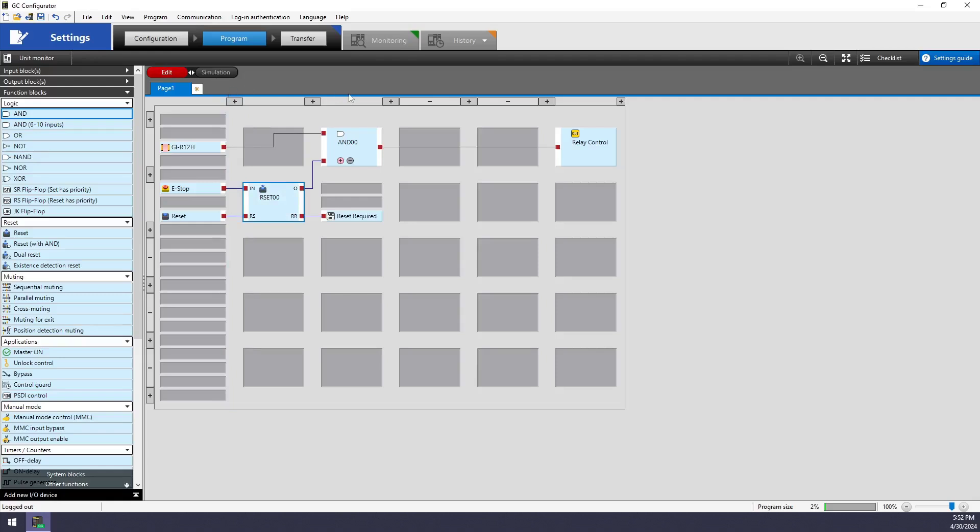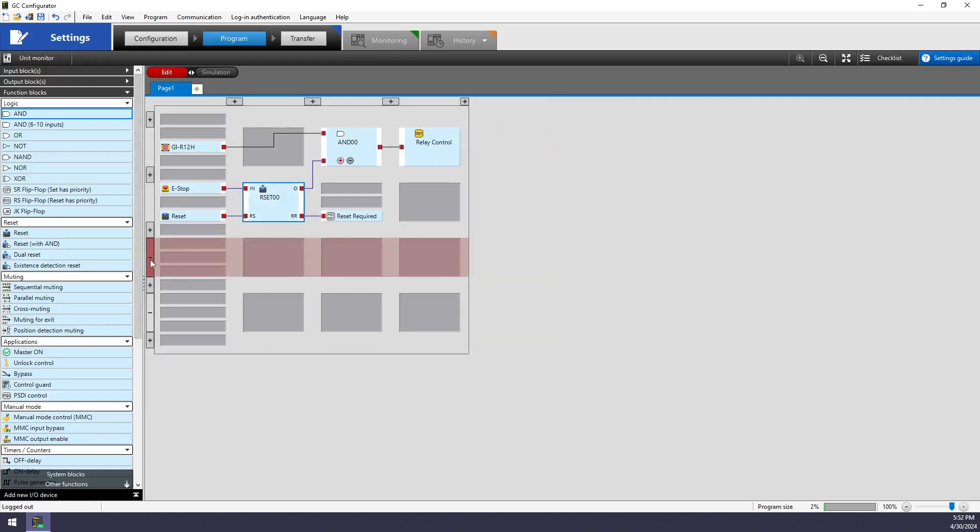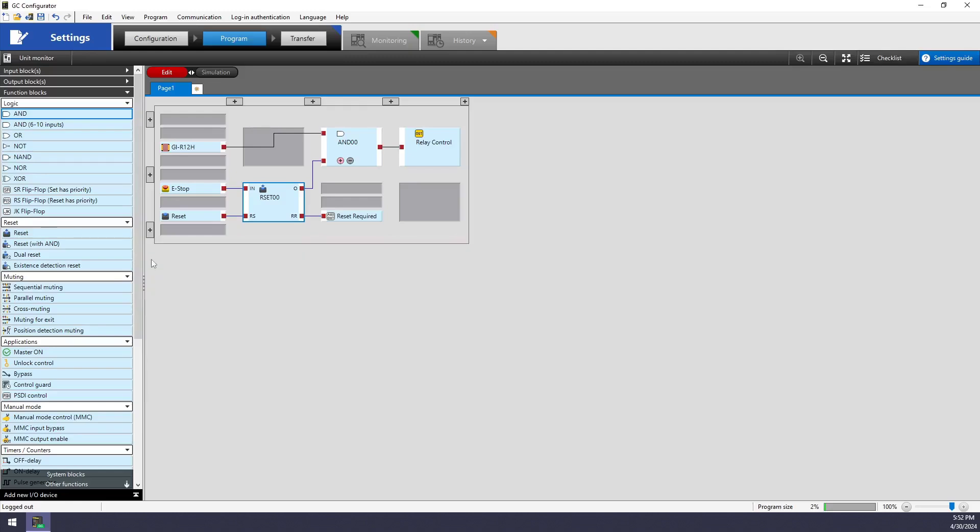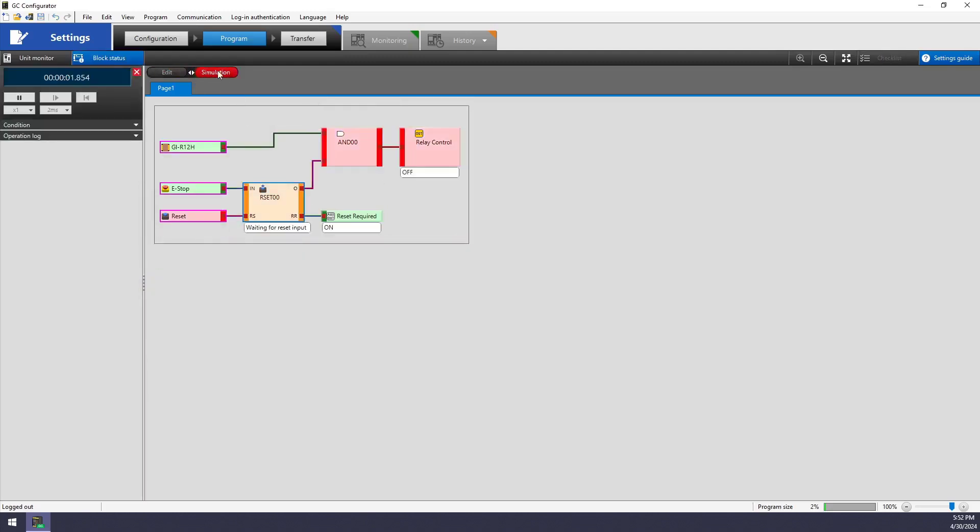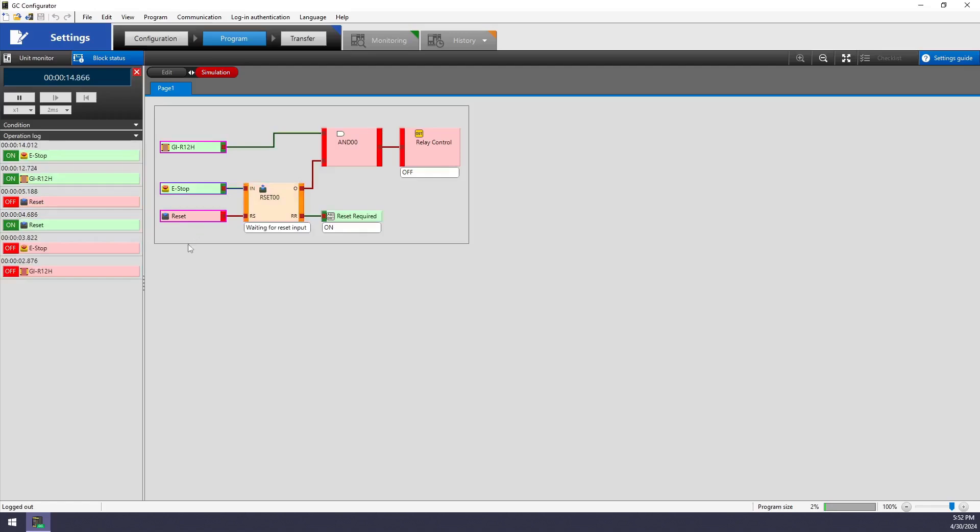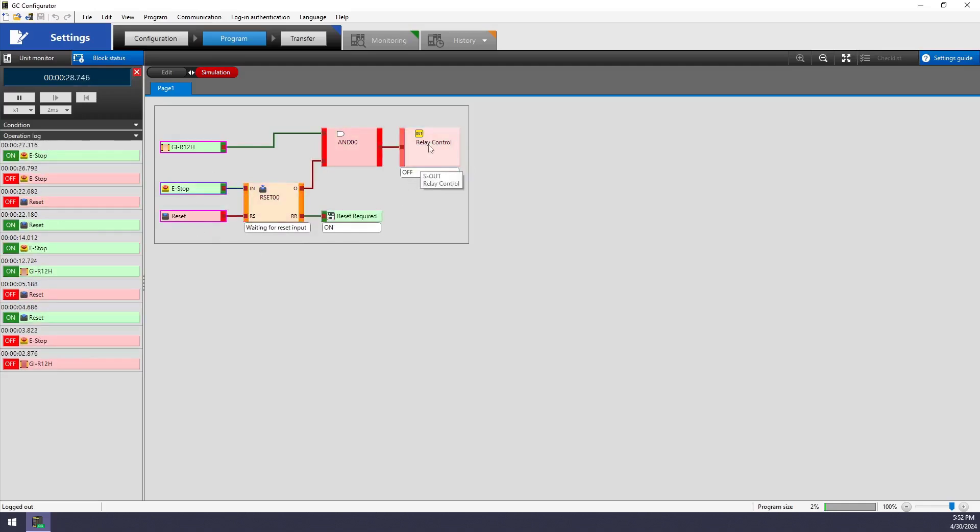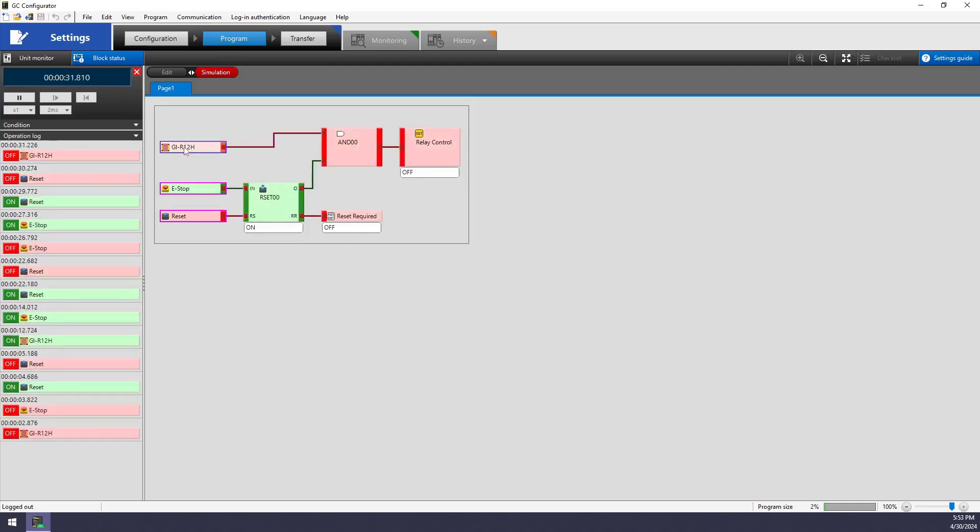I'm really done programming now, but what I always do before I transfer it over to the GC is to simulate and make sure that the function is as I intended. So by clicking on any of these input devices, you can simulate them going from a safe condition to an unsafe condition or pressed versus not pressed. My curtain and e-stop are safe. The GC tells me that I'm waiting for a reset input and my reset required indicator is currently on. As soon as I pulse the reset button, then everything goes green. The e-stop is manually reset while the curtain is automatically reset. So I'm happy with this operation.